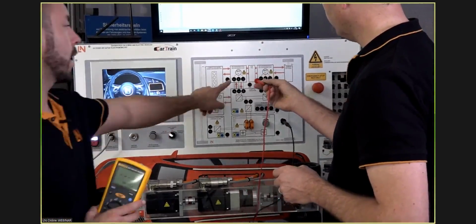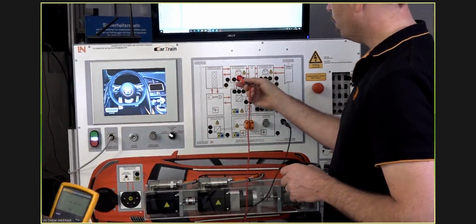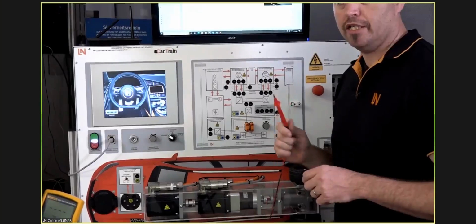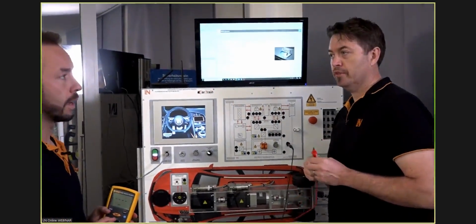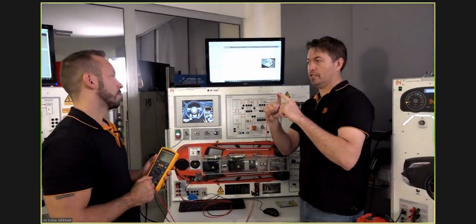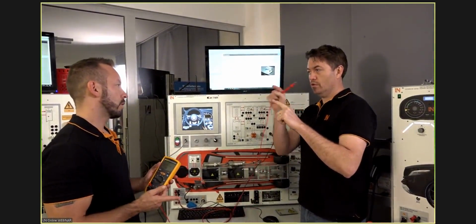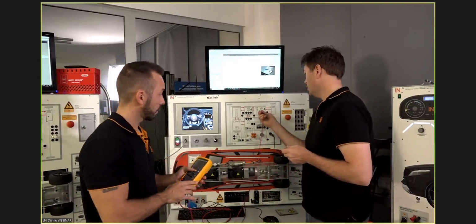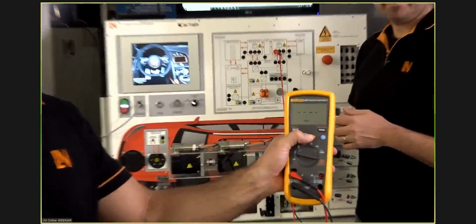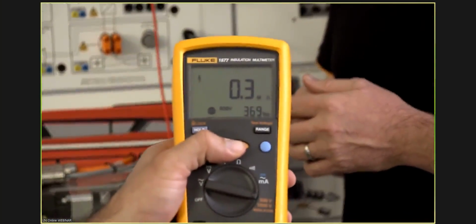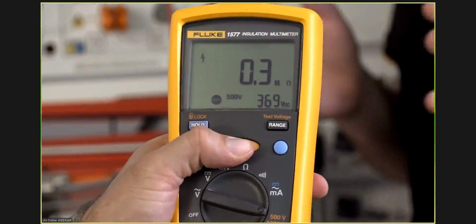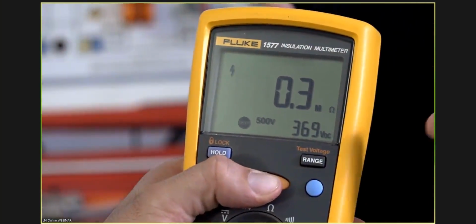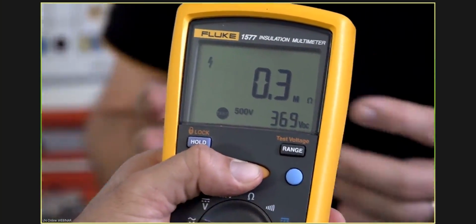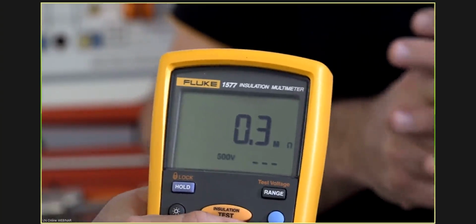Why shouldn't we measure the other ones? Because if we have a look at the motor generator, it's in a star or a delta fashion. Yeah. That means all of the phases are connected together. So if we measure 1 and there's a fault, we're going to be measuring all 3. Okay, that's good. So if we then go to MG2. Oh! And we can see here, there's a real problem. This is now 300,000 ohms. So 300 kilo ohms is what we're showing there.